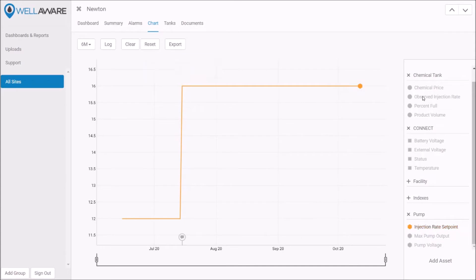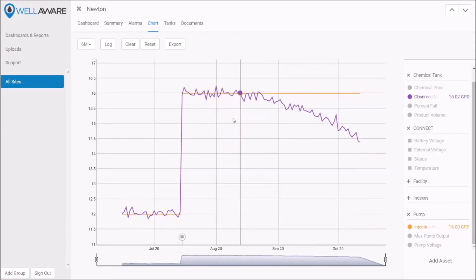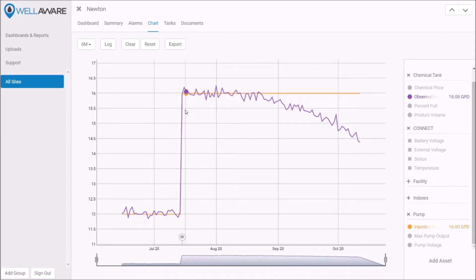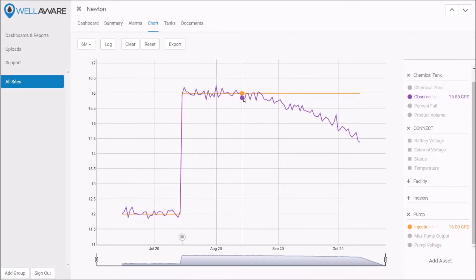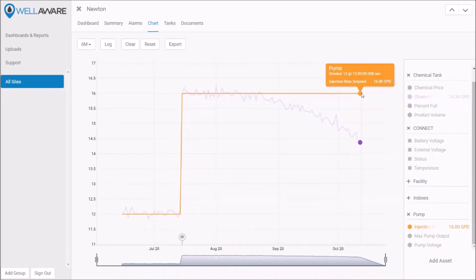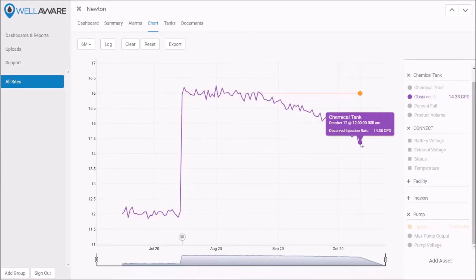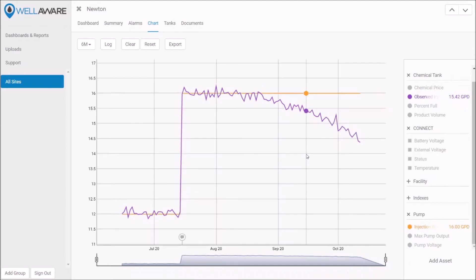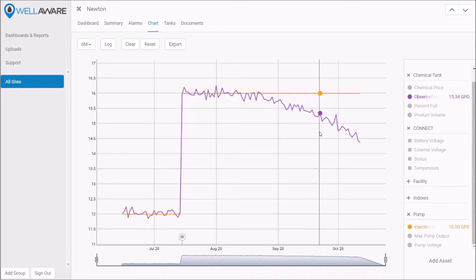Now let's look at the observed injection rate. Ah, here's the issue. While we saw that for the most part through the warmer months we were actually hitting the target injection rate, we start to see that tailing off in the colder months. We're trying to do 16 gallons per day today, but because of a calibration issue we're only injecting about 14 and a half gallons per day. That might not seem like much, but it's a problem we need to get addressed.